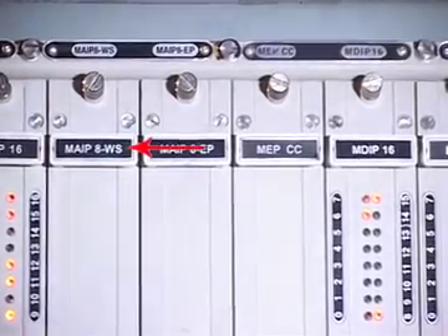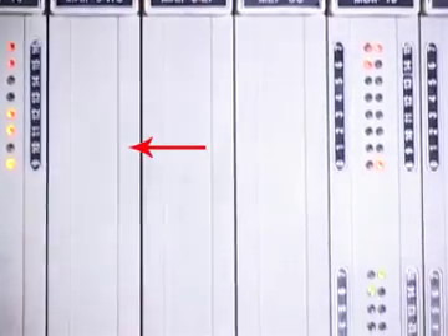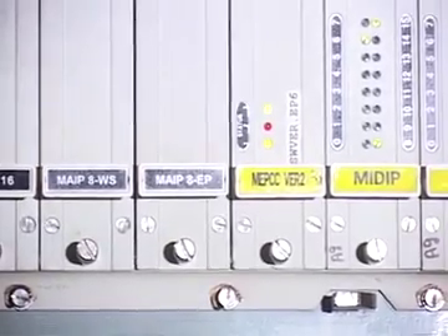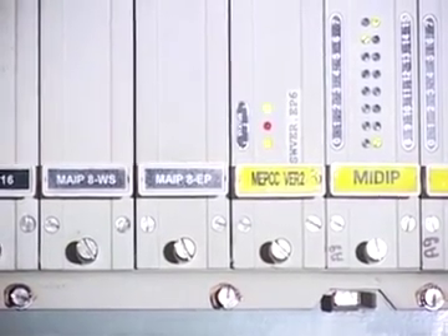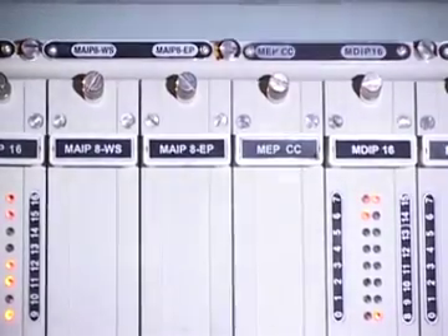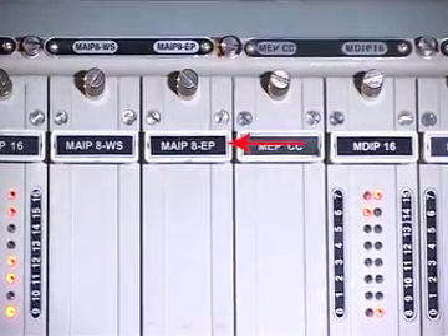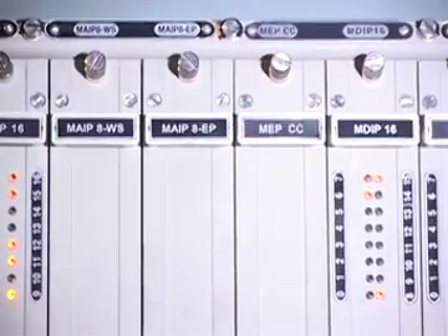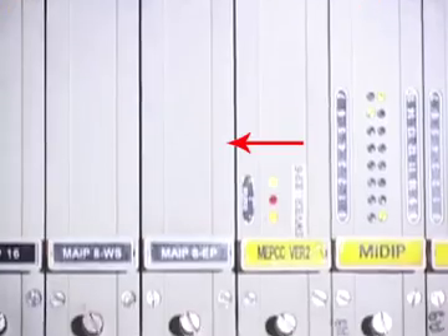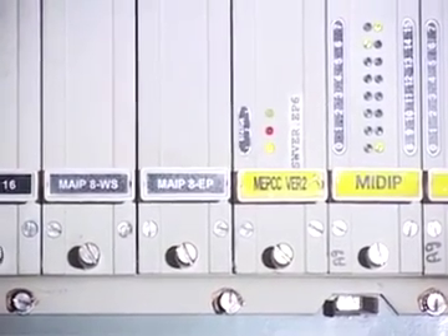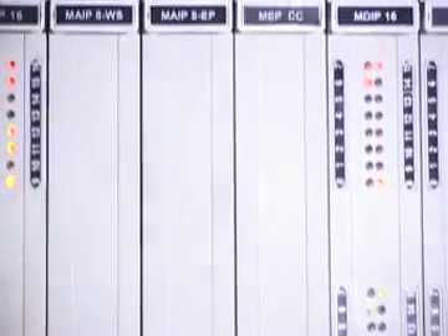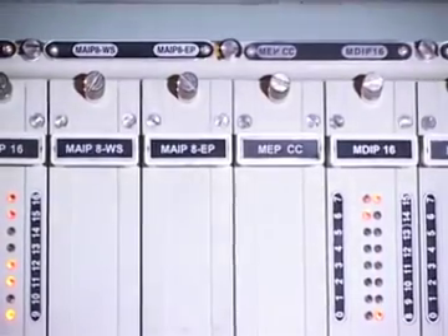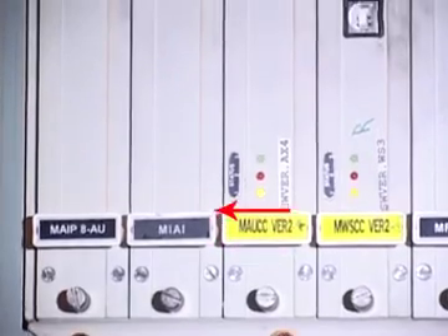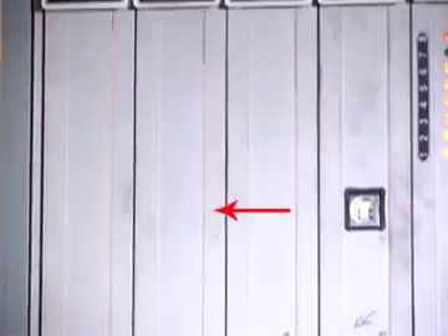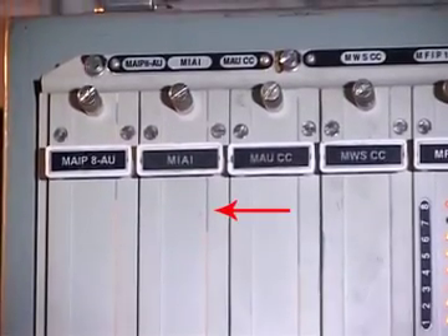Analog input card MAIP8WS. This MAIP8WS card is connected between the MWS-CC card and ADB2. Individual traction motor current signals are mainly connected to this card. Analog input card MAIP8EP. This MAIP8EP card is connected between the MEPCC card and ADB3. All the excitation-related parameters are mainly connected to this card. Improved analog input card MAIP16 or MIAI.